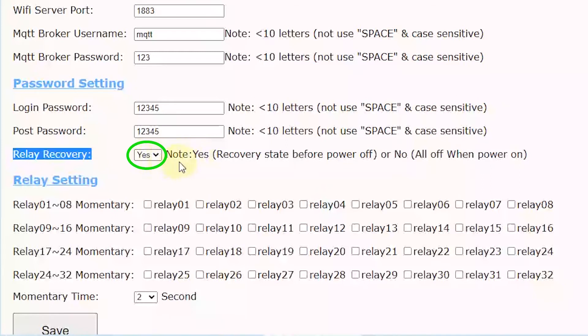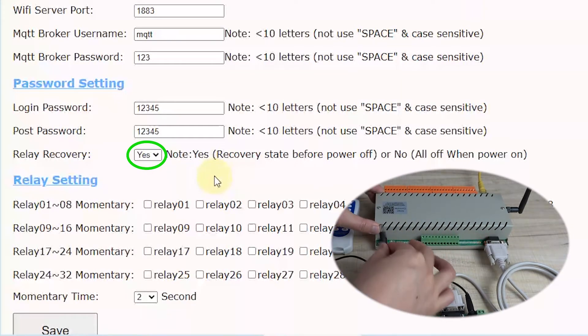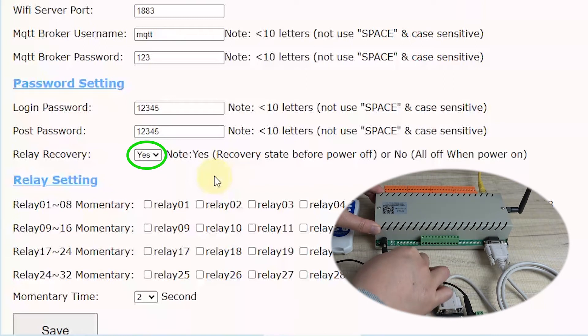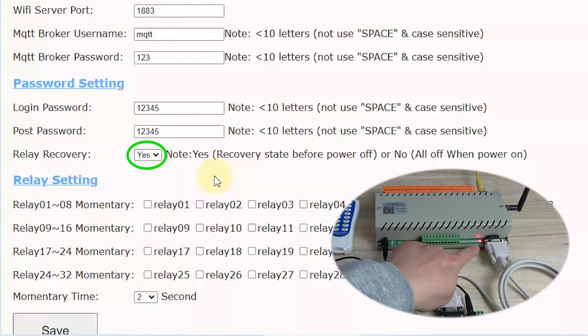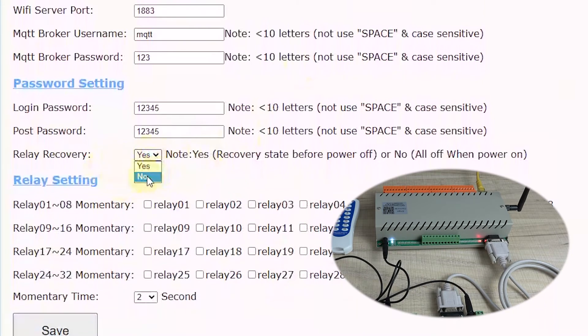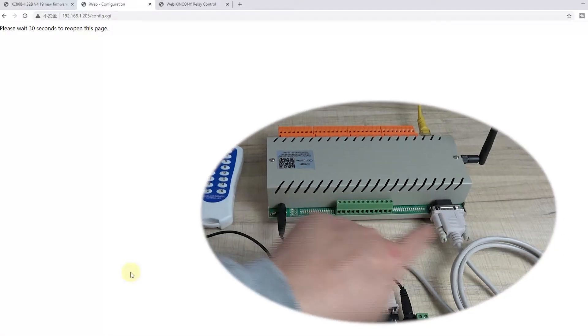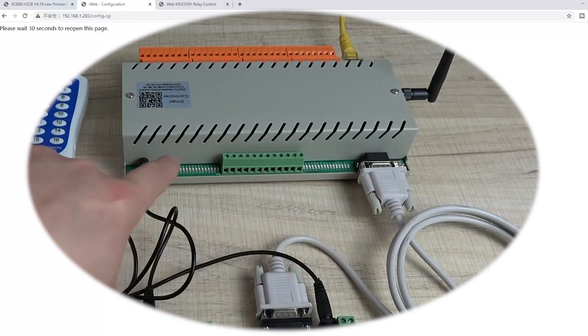If I press yes, we can see the controller now has Relay 1 and Relay 2 on. When I power off and power on again, after the controller restarts, Relay 1 and Relay 2 will recover to the state before the power was cut. If I set this option to no — not remember — and press save, you can see that after the controller starts up, all relays become off.